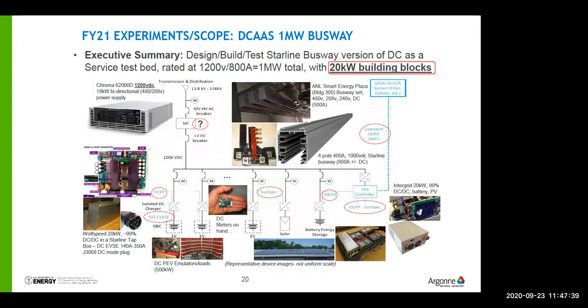This can range from the size of a chest freezer to the size of a semi-trailer or multiple semi-trailers. Taking medium voltage to DC, thinking about the numbers, if it's 13.2 thousand volts down to 1,000 or 1,300 volts DC, that's a 10-to-1 turn down ratio, not that big. That's the big deal about distributing above 1,000 volts DC, 1,000 to 2,000 volts, which you'll see in subsequent slides.